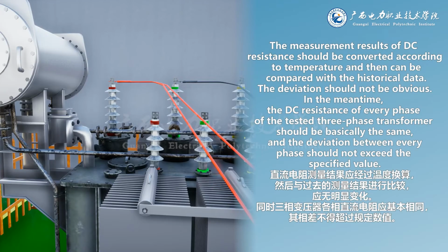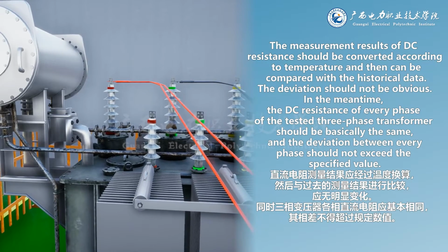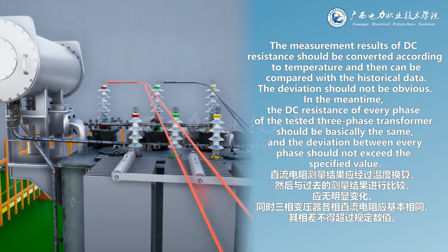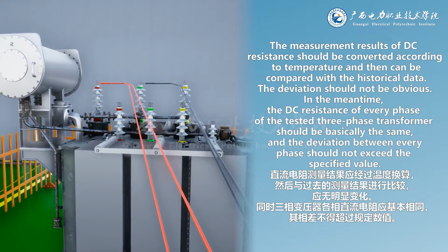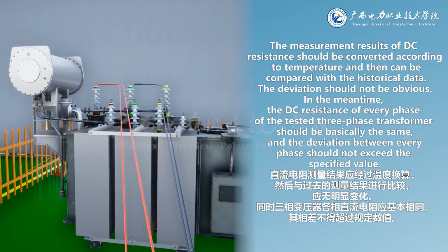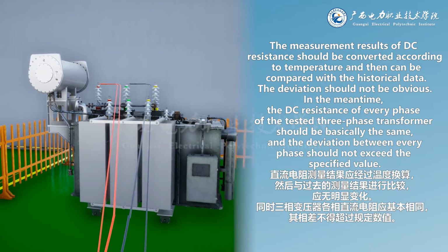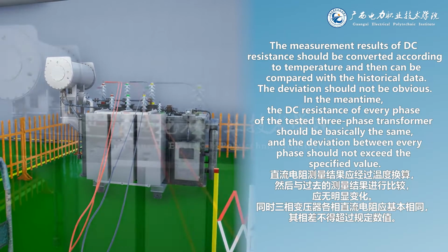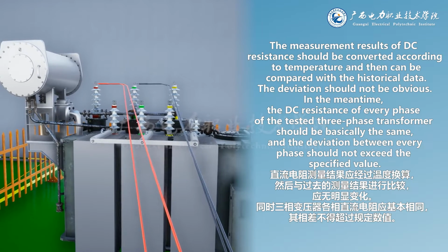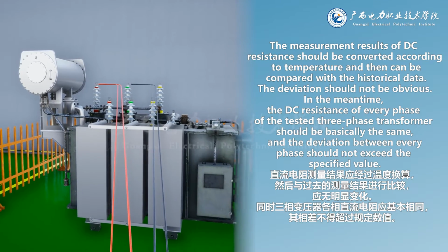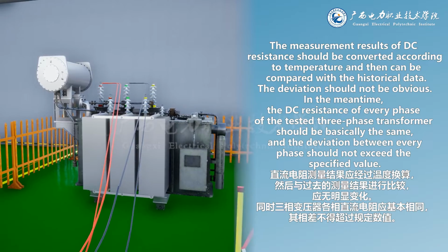The measurement results of DC resistance should be converted according to temperature and then can be compared with the historical data. The deviation should not be obvious. In the meantime, the DC resistance of every phase of the tested 3-phase transformer should be basically the same, and the deviation between every phase should not exceed the specified value.